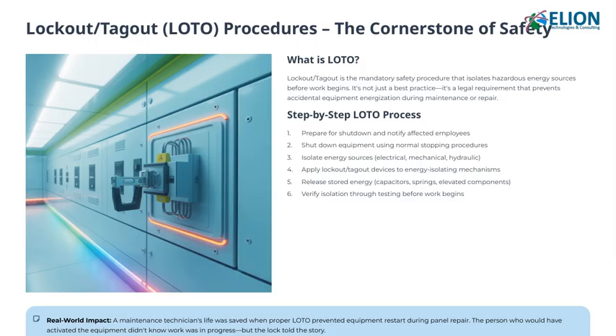After isolating the energy sources, you apply lockout or tagout devices to the energy isolating mechanisms. This ensures that the equipment can't be accidentally turned back on. The next step is to release any stored energy. Think of capacitors, springs, or elevated components that might still pose a hazard. Finally, before starting work, you verify that the equipment is truly isolated through testing.